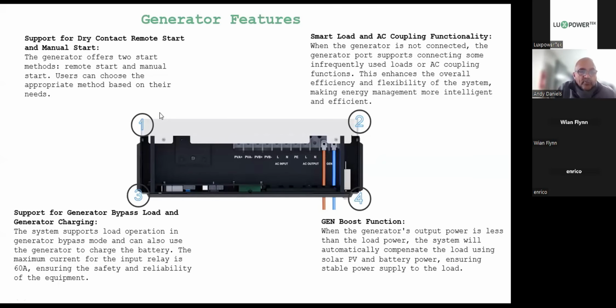All right, so the point number 1 here that we're going to talk about is support for dry contact and remote start. Here we have dry contacts, and you will be able to see them on the connector ports. Dry contact allows you to remote start a generator that has an automatic start, an ATS. An automatic start function. ATS is an automatic transfer switch. It has an automatic start. It will work on the maintenance page. There's a setting for generator, and it will work either on, it has 2 flags. So if you've selected voltage, then it will use the lower voltage to start the generator and the higher voltage to switch it off. If you choose SOC, it will choose the lower SOC to start the generator and the higher SOC to stop the generator.